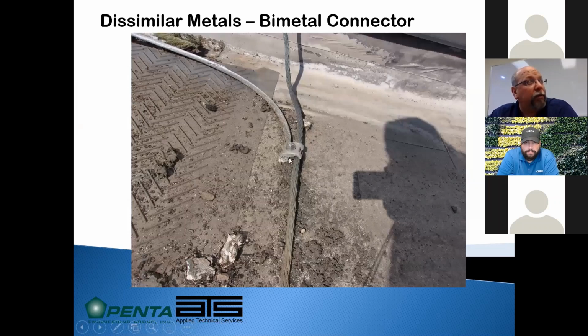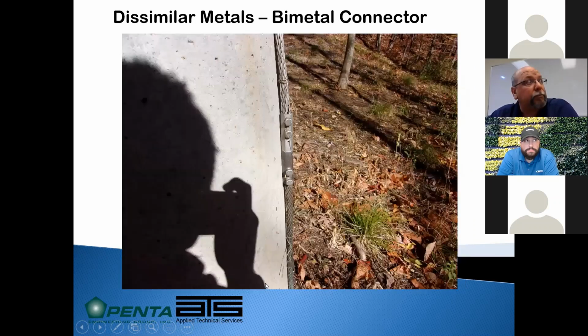Here we have an example of a bimetal connection. It's kind of hard to see in this photo, but there's a thin wafer that runs between these two clamp pieces, and one side is copper and the other side is aluminum. So we can mix the metals as long as we're using a part to join them that is designed to prevent that galvanic corrosion from happening. Here's another example of an inline bimetal connection. This is part of a down conductor that was mounted on the exterior of the building and routed to the ground.